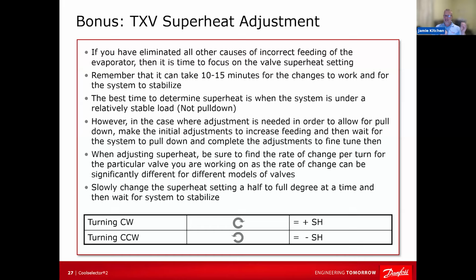As soon as you open or close that TXV, you're going to see a change, but it ain't going to stay there. It is going to fluctuate until the ripple, like in a pond, until that change in refrigerant balances itself out and it gets close to not hunting anymore. That's what we talk about when we say 10, 15 minutes.